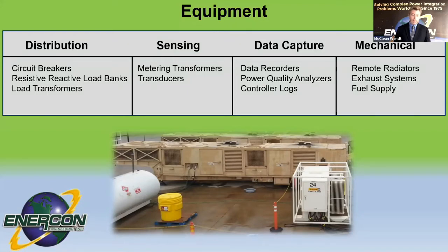Sensing, we've got metering transformers and transducers. Those are sometimes external. We put our own external ones on the units to test them, or sometimes we can interface with the generator's own metering transformers. And those will report to a data capture device. We have data recorders and power quality analyzers that we use to record and also to evaluate the performance of the units. Depending on what controller is on the generator, we can also access the logs and do that for an additional record of the test.